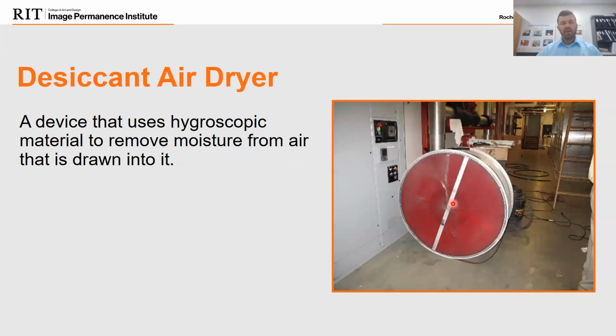Desiccant air system, desiccant wheel or desiccant dryer. It's a hygroscopic material that rotates inside a mechanical system. As this wheel rotates, some of the air is going to come in contact with the air from your facility. Some air is going to come in contact with regeneration air.